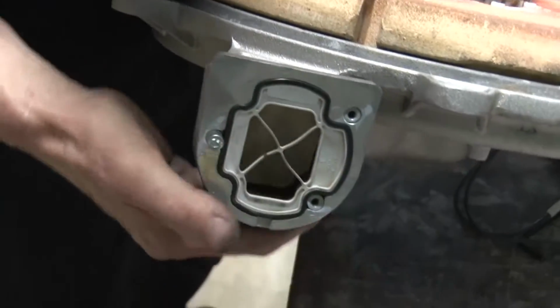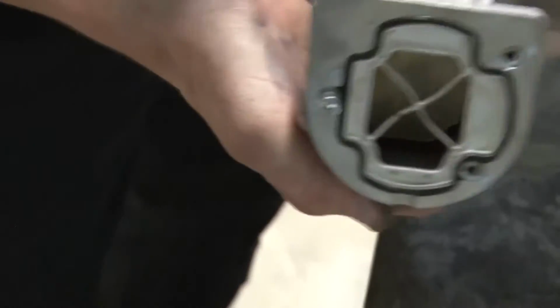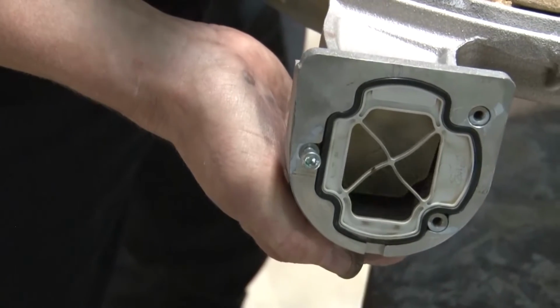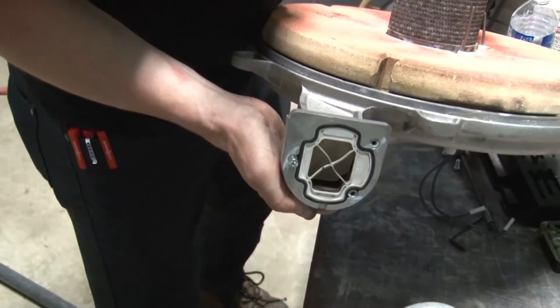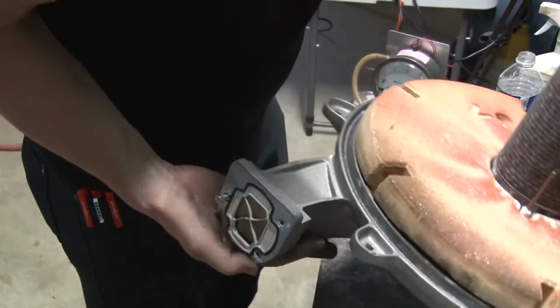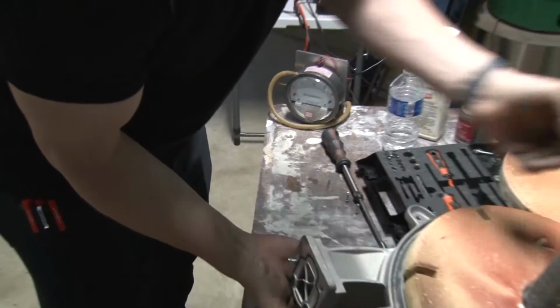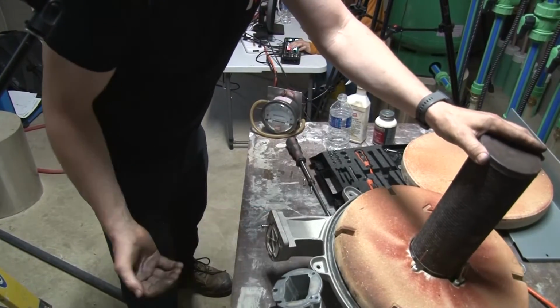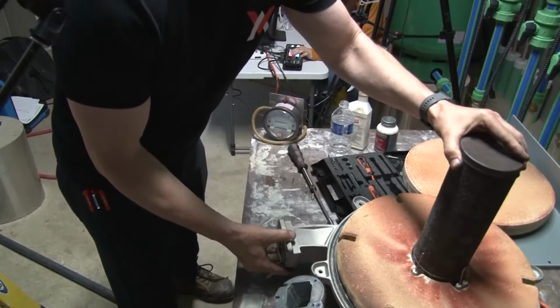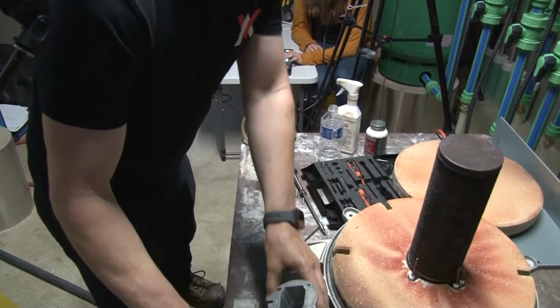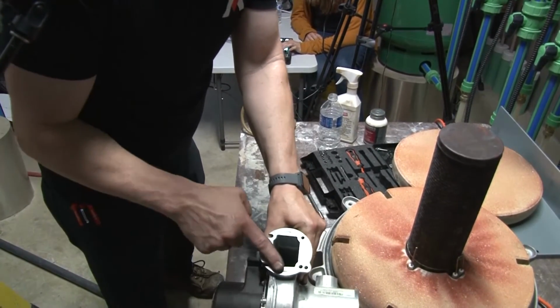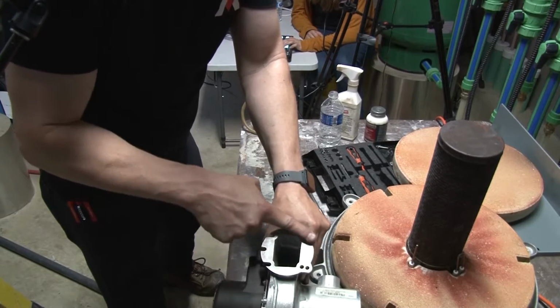But I'm looking at that little flapper in there, so you can see how that operates and it's doing its thing. So when we have a downward force on that flapper, it's like a check valve. It closes off and air can't flow. If I have basically an upward force, it pushes that little membrane out, and then away we go. Another area to check while we have it open is right here on your burner flanges.